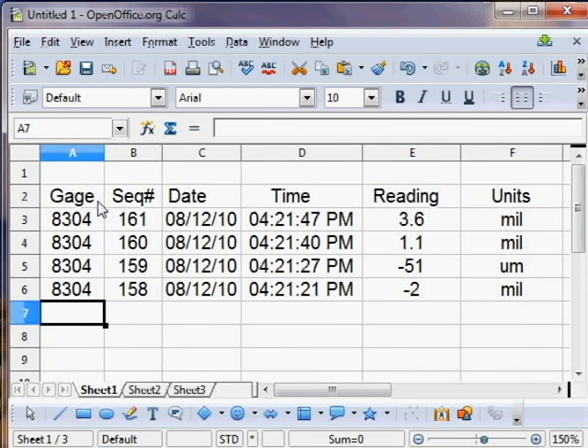Different columns will indicate from left to right the gauge serial number, the measurement sequence number, the date, the time, the replica film thickness measurement, and the measurement units in mils or micrometers.